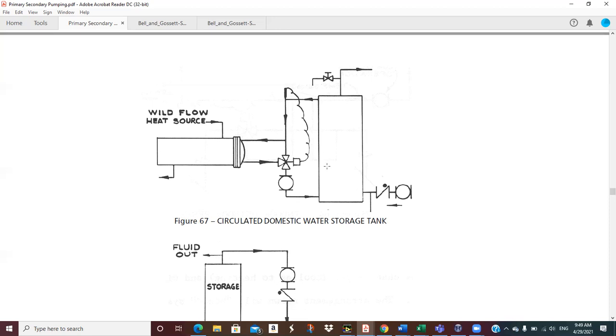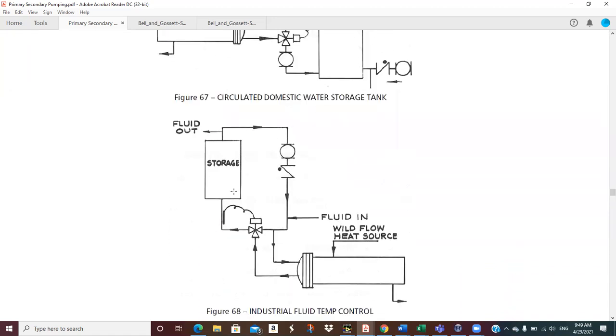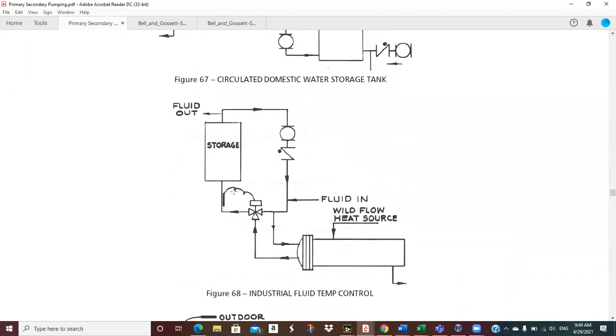This circulates all the time. The cold water comes in here, mixes immediately in the tank, and this circulates continuously, and we bleed in heat as we need it here. When this valve lets some of this hot water into here, then some of this return flows through the heat exchanger. So, bingo. Let's see, industrial fluid temperature, similar sort of thing, just a different application.